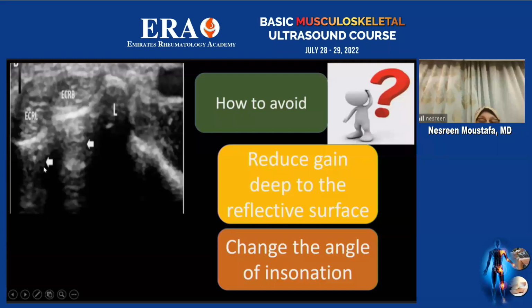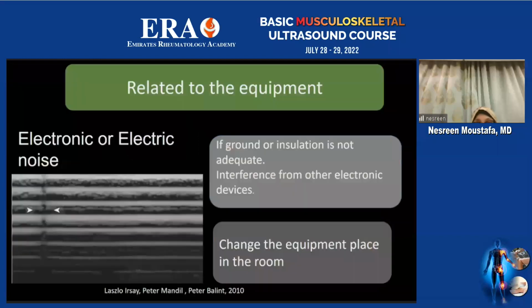How can we avoid this? We can reduce the gain deep to the reflective surface, so we will not see any shadow here, and we can change the angle of insonation as well. Sometimes there are artifacts related just to electrical noise, maybe because of no earth or no ground or something like that. So we change the equipment's place in the room, and it will appear in this shape.